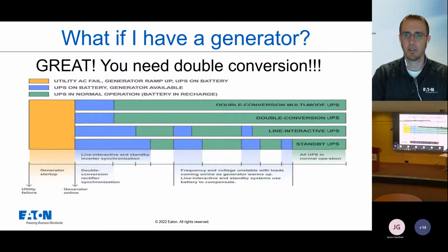Now, UPSs are well built, but somewhere in there could be the opportunity for a dropped load. And even though it might just be for one second, if you have a critical device behind, say, a line interactive UPS and the power turns off for one second, that could be enough to corrupt your data and ruin your day.